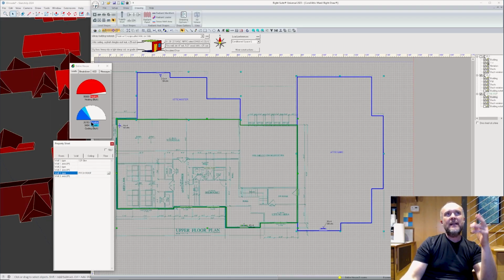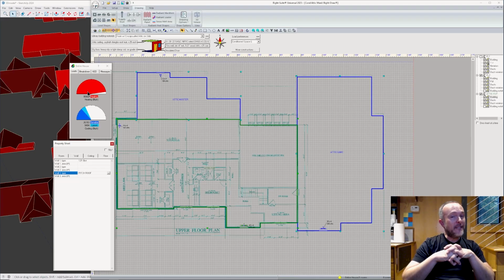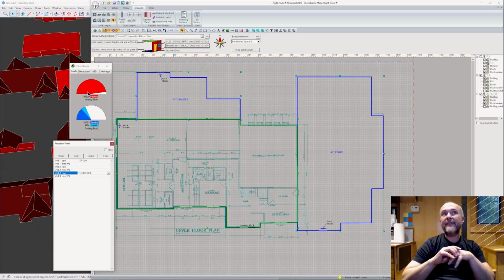I will say as a last note here, this discrepancy between 96,000 heat required for this house and 36,000 required for cooling, this number is wildly wrong. The red number in wintertime is overestimated for high performance homes that are going to be of this air tightness by somewhere between 50% and 120% too big. And this is not just me, this is other people, and you can ask around other HVAC high performance people who are working in this space. That means that we're just going to go ahead and automatically divide this in half. And we get to the point where we could install a 3.5 ton heat pump and likely have it work for this entire house.